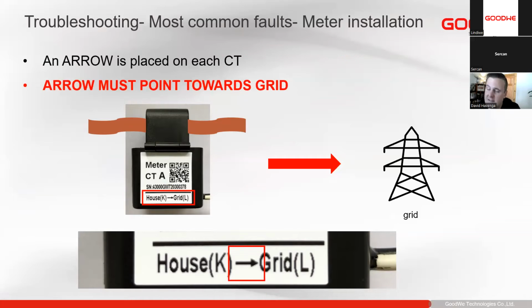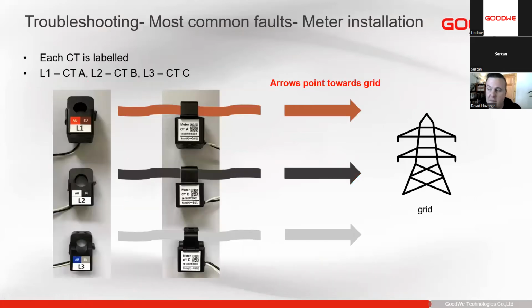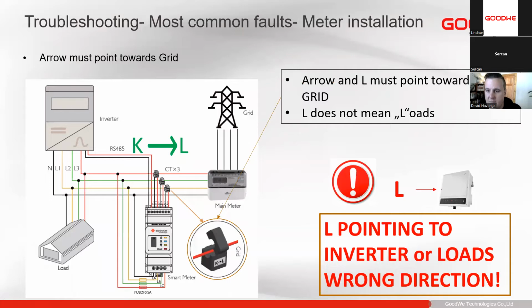So on all of our CTs, all of the years I've been working with GoodWe, all 6 years, I've never had the sticker be wrong. It's always correct on the CT. The arrow must always point towards the grid. So it's K to L, house to grid. It's stamped on the CT, you'll always see it there. Please always make sure it is correct. Same with three-phase, you get CTA, CTB, CTC. Also with the K to L, house to grid. We always try and reaffirm this over and over again. K to L, so it's from the house to the grid. The arrow must always be pointing towards the utility.